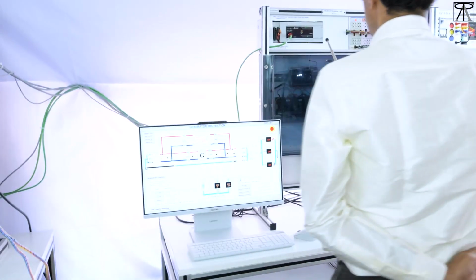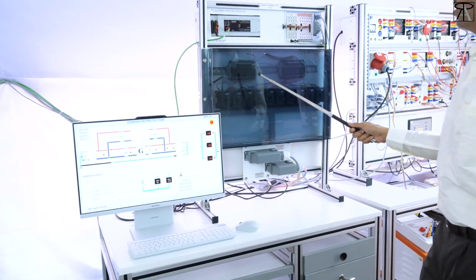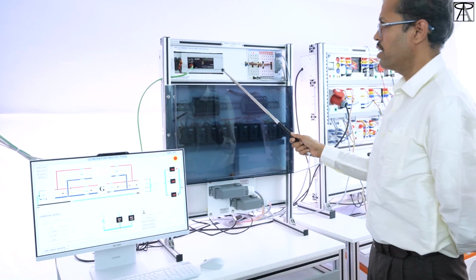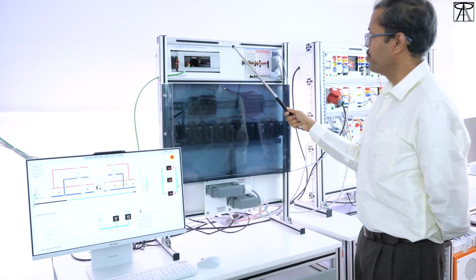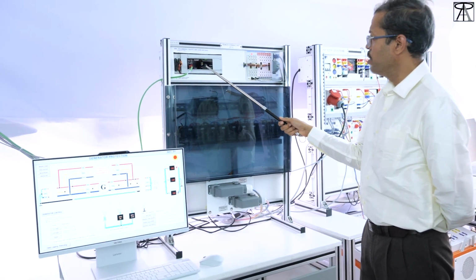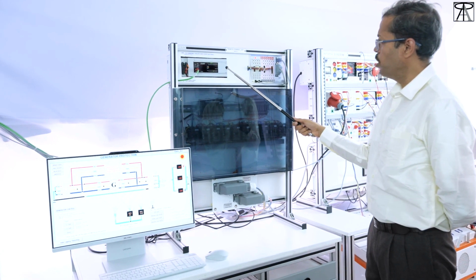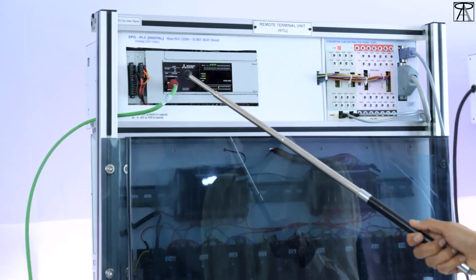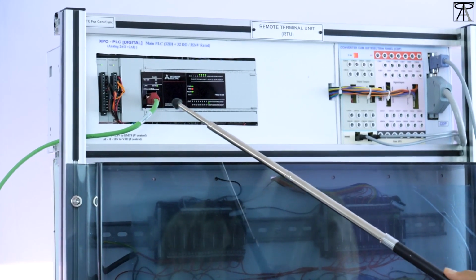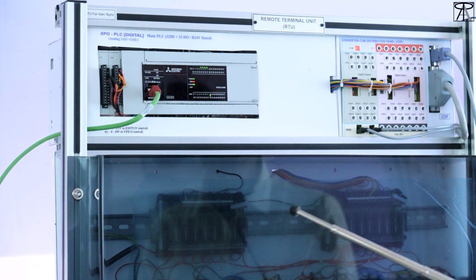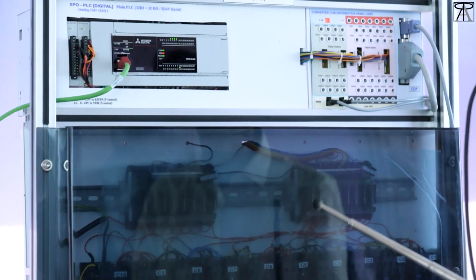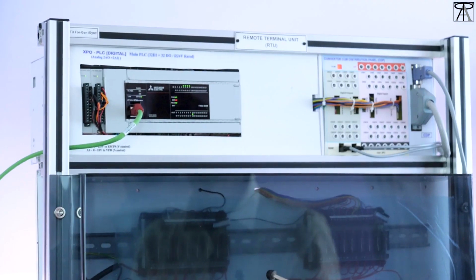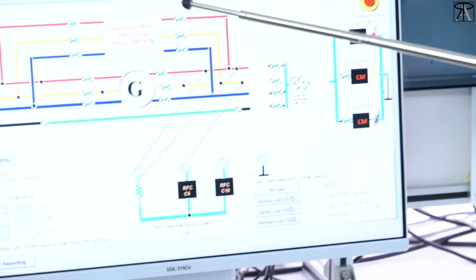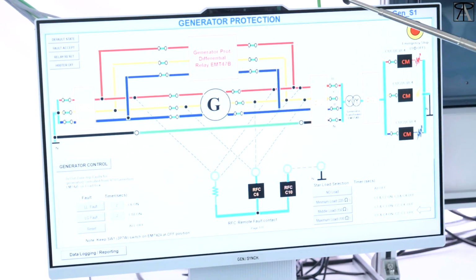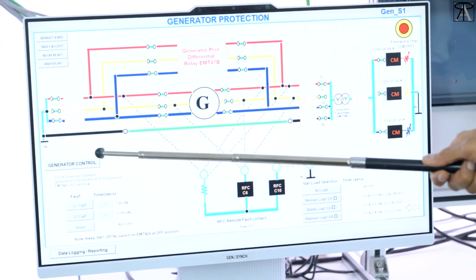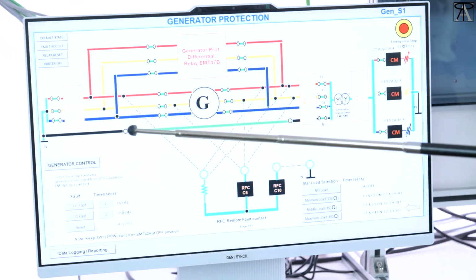This is the synchronization setup to control the remote terminal unit, generation and synchronization. We used an RTU, remote terminal unit. This has a Mitsubishi PLC with more than 32 inputs, 32 outputs, 2 analog outputs and 2 analog inputs, with MODBUS communication and Ethernet communication with SCADA compatibility. These are relay contactor panels used to control the motor and loads. This is the SCADA software screen. This is the HMI touch panel. You can touch it, generation, voltage will come from the generator, and the motor will turn on.